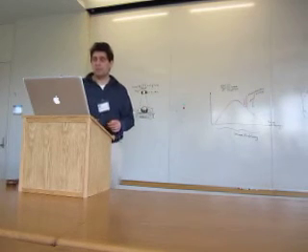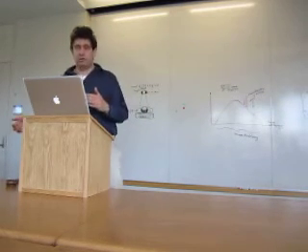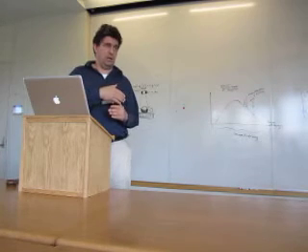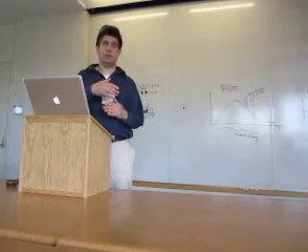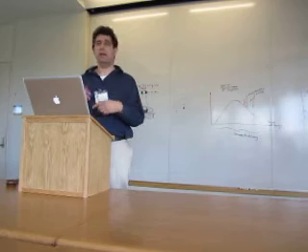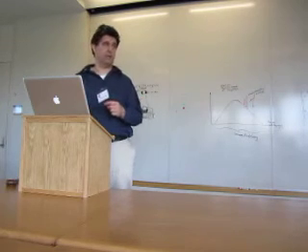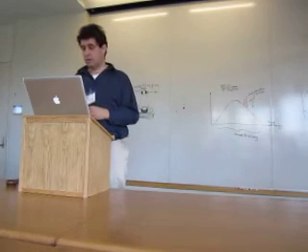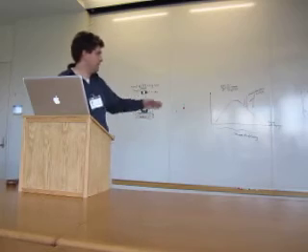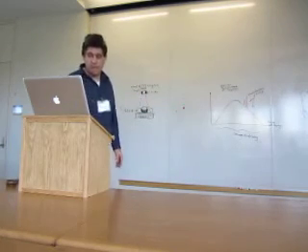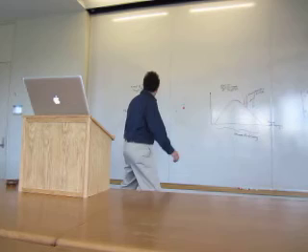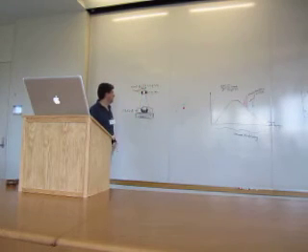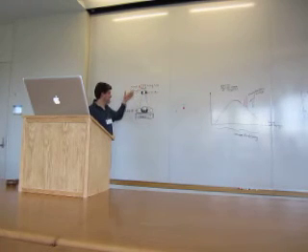It basically is when the nucleus is involved in changing the direction of the electron. And when you change the direction of a traveling electron, you're accelerating it, and it shoots off some energy in the way of a photon. So you produce a broad band of energy. This broad band of energy, then, is what comes out of our tungsten target from this X-ray tube.